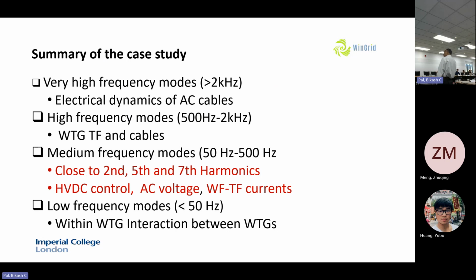Medium frequency mode, they are close to second, fifth, and seventh harmonics. This is where actually we saw sometimes instability in HVDC control, AC voltage, and wind farm transformer currents.